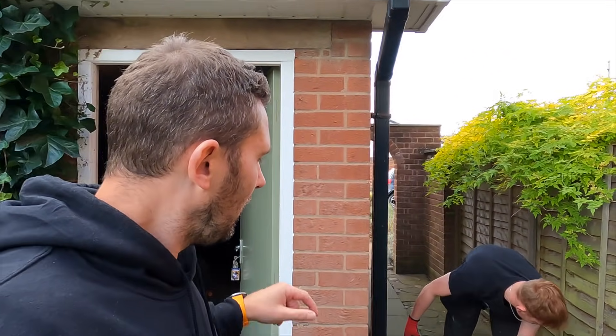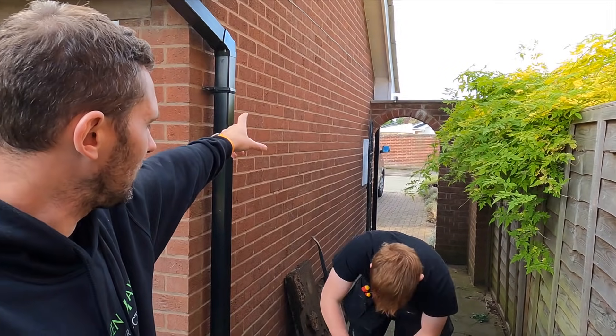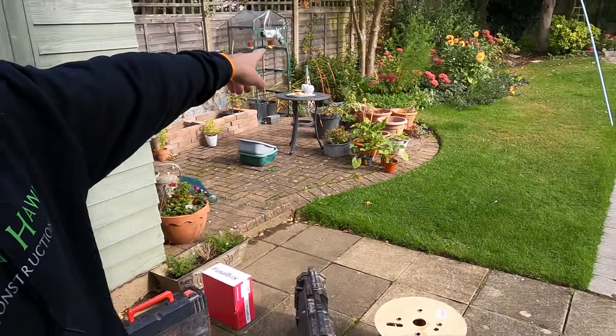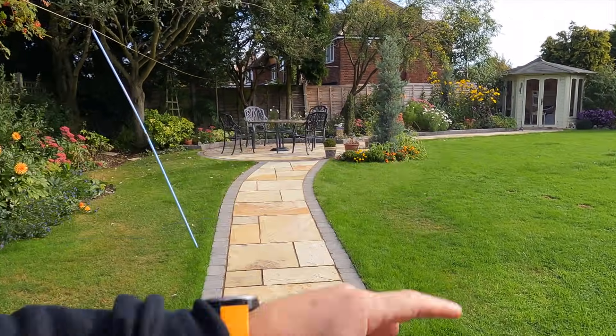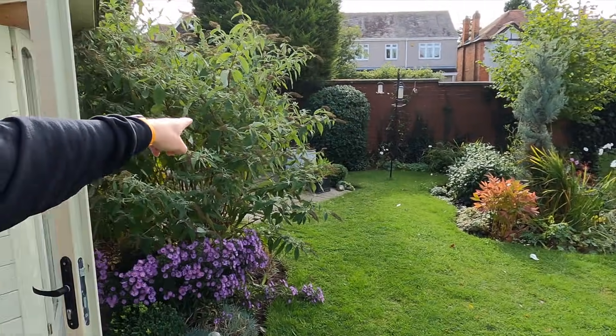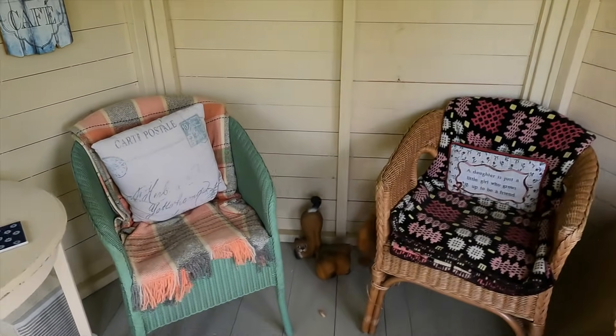So that's what we're up to and the video is sponsored by Tradeify. Job today — I've come here a day early so we won't get it all done today, we'll be back. The plan is: the consumer unit is in the garage to the side, we're splitting that and putting another little separate one in. Jack's already cracking on with the trench. We're going to be running our armoured all the way down, all the way around the outside of the building and to that wonderful little summer house. In the summer house we've already got a little consumer unit that's fed off a spur off a spur inside the living room, runs all the way down through here into this little summer room. It's been installed very, very poorly — it's not glanded, wrong size cable for everything in there.